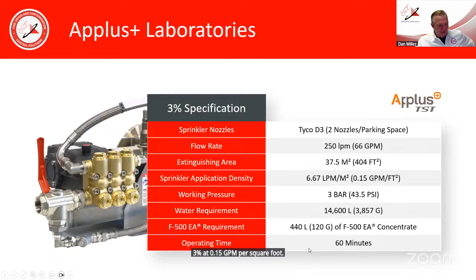Working pressure was 43.5 PSI or 3 bar. The total water requirement was only 3,857 gallons, and that was for the entire 60-minute test of flow. And then the F500 EA requirement for that same time period was only 120 gallons total. So if we reverse the math out of that, 60 minutes, 3% at 0.15 GPM per square foot, you come up with the total used was 120 gallons.